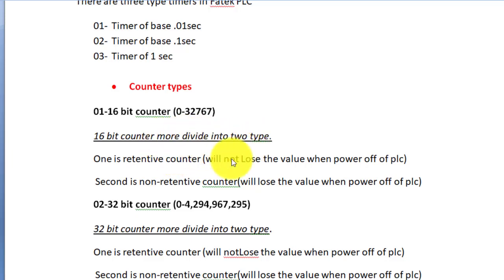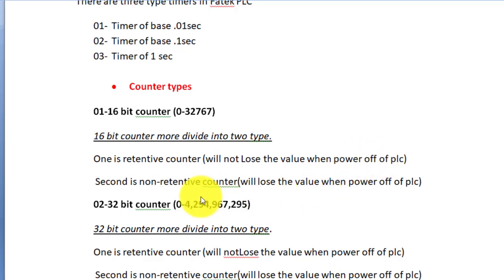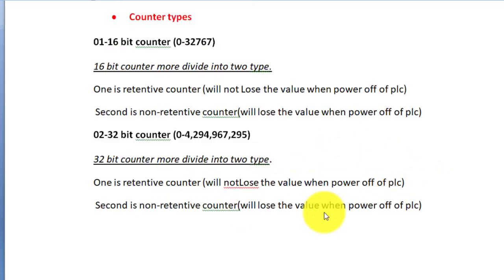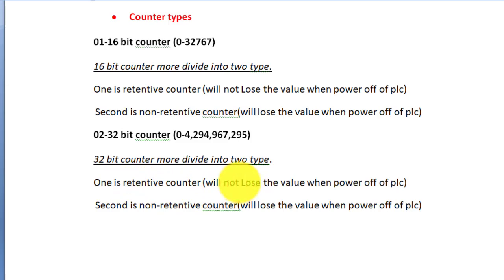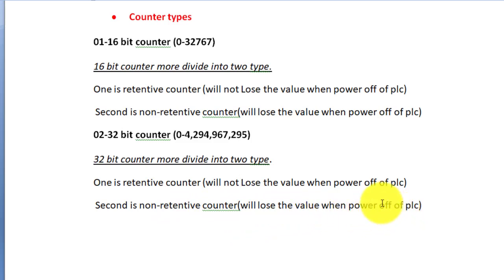The 16-bit counter is divided into two types: one is the retentive counter and the second is the non-retentive counter. Retentive counter will not lose the value when power of PLC is off. Non-retentive counter will lose the value when PLC power is off. The 32-bit counter also has two types: retentive and non-retentive, with the same behavior regarding power loss.